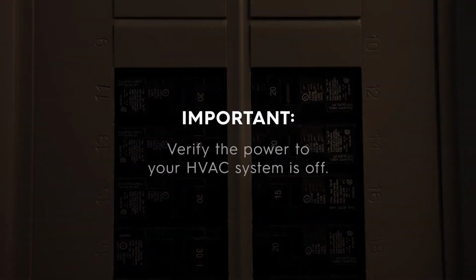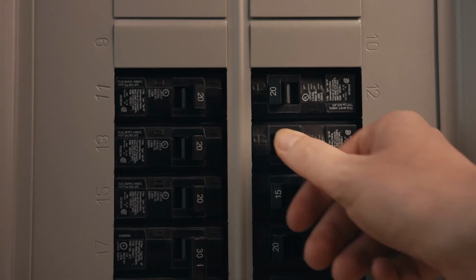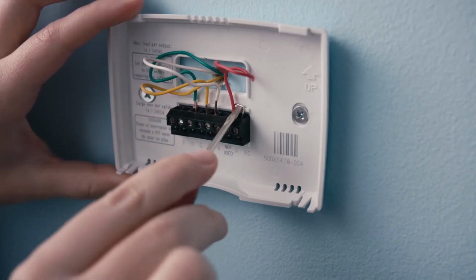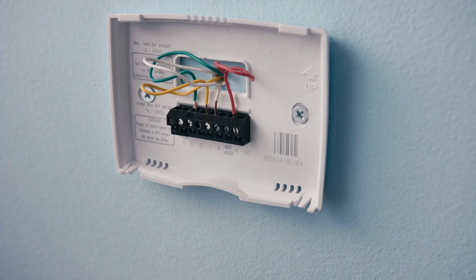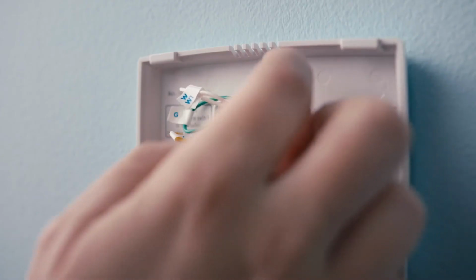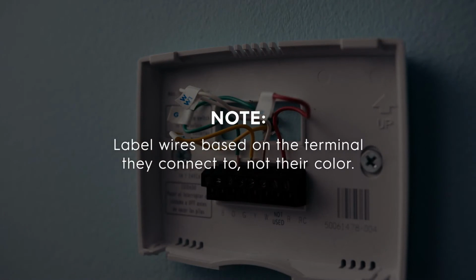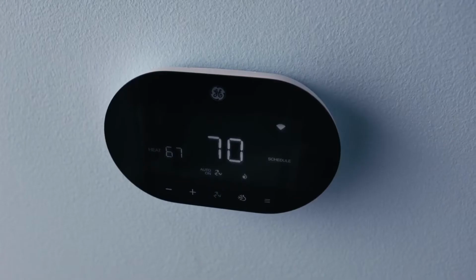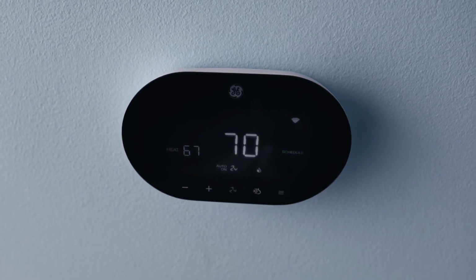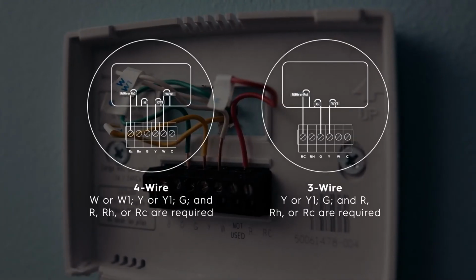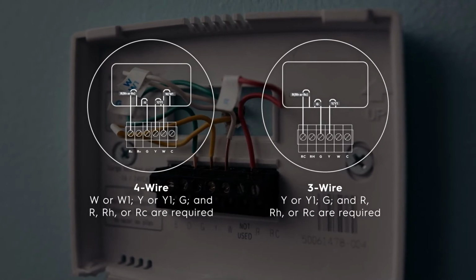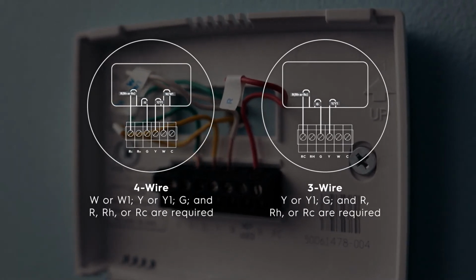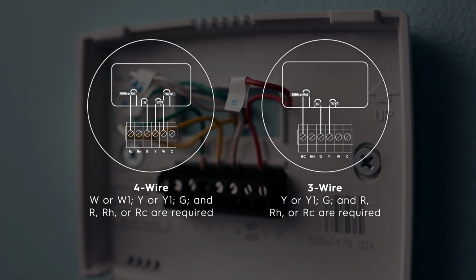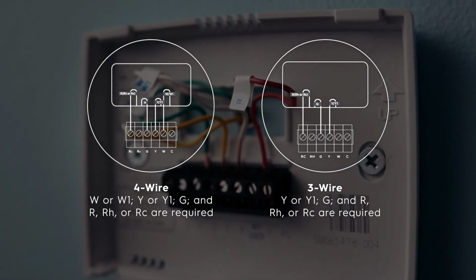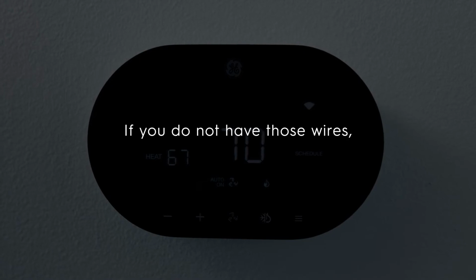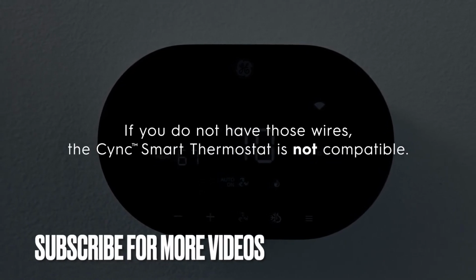The first step is to verify that the power to your HVAC system is turned off. Step 2. Remove any jumper wires. These connect two terminals such as RH to RC. Using the labels provided, label your wires based on the terminal they connect to, not on their color. Step 3. Ensure your wiring is compatible with the Cync Smart Thermostat. Either these 3 or 4 wires must be present for successful installation. The W or W1 wire, the Y or Y1 wire, the G wire, and the R, RH, or RC wire. If you do not have those wires, the Cync Smart Thermostat is not compatible with your wiring.